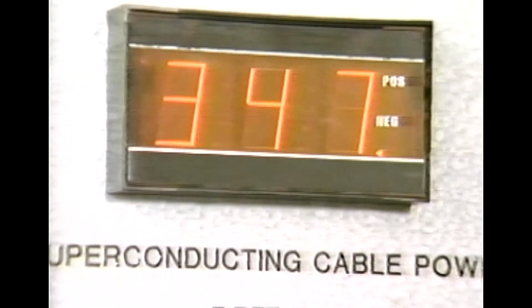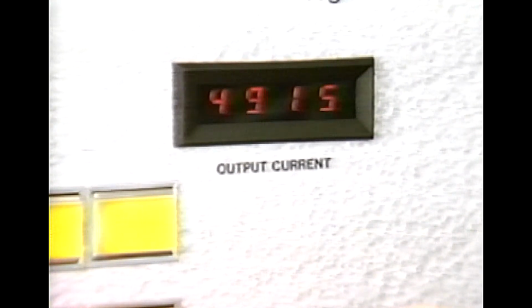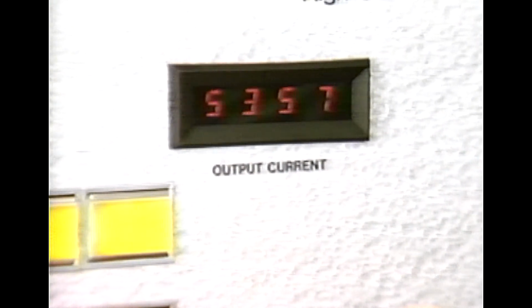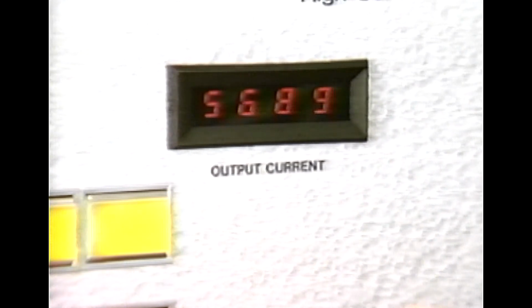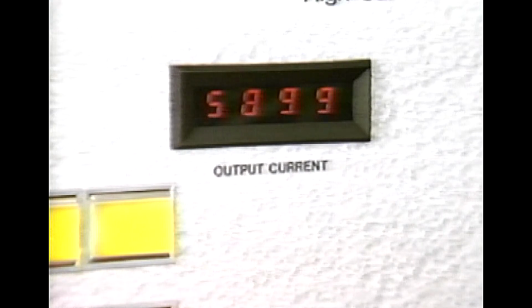After verification of performance at 333 MVA per cable, the power level is raised. The cables are designed to run at 500 MVA for 30 minutes, a condition corresponding to emergency levels on the network. The extremely high reliability of the U.S. electrical transmission network is in part due to the ability of all components to carry extended overloads, so that faults do not cause a chain reaction failure or blackout of the whole network.